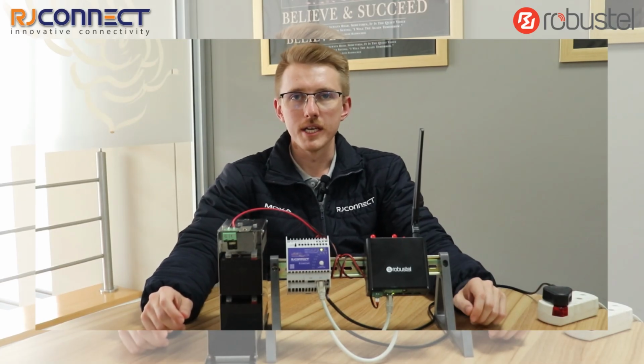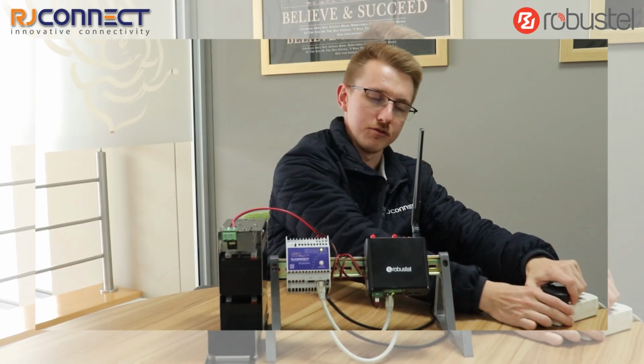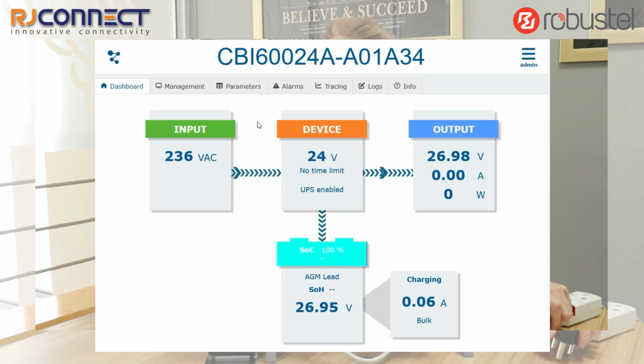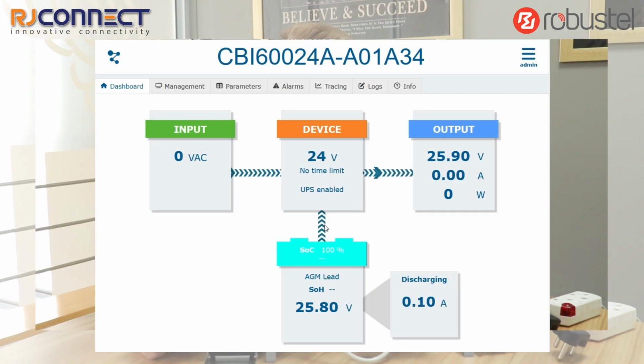We will now simulate a mains failure by switching off the AC supply to the RJU. The purpose of this test is to show that the connected 24-volt load remains powered while the RJU transfers to battery backup operation. The two sealed lead-acid batteries provide a 24-volt DC backup supply during the interruption.